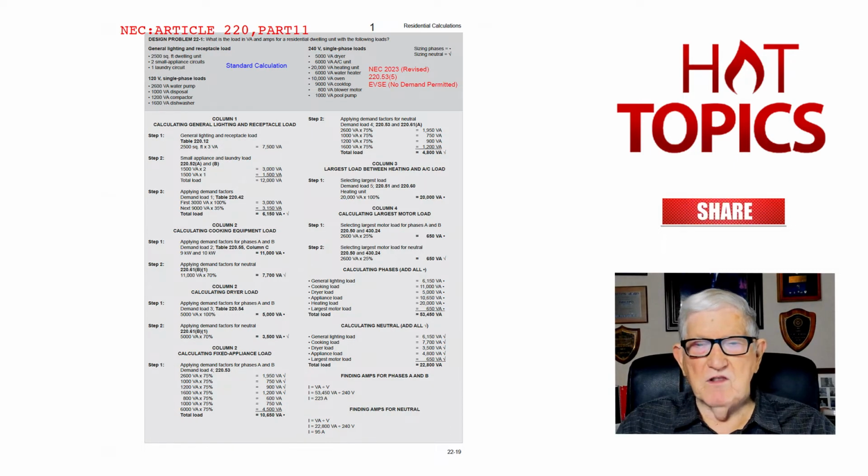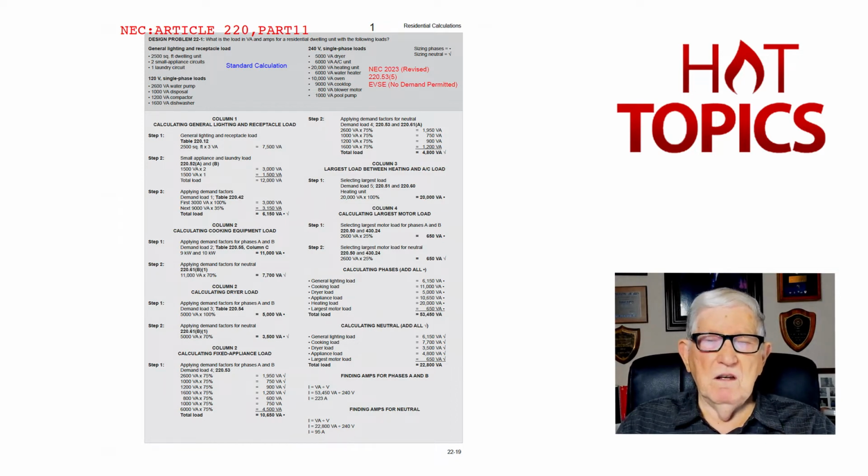So that would be the size conductor that we would need. So we would need a 4-aught, wouldn't we? By this calculation. I kind of remember that. We'd need a 4-aught. And then for the neutral, it's 95 amps. Then we would need at least a number 3, see, if we had 75 degrees C terminals, which we won't get into at this point. But remember these totals, we'll call them again.